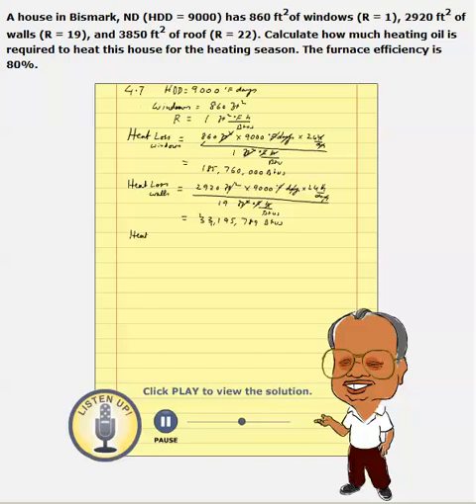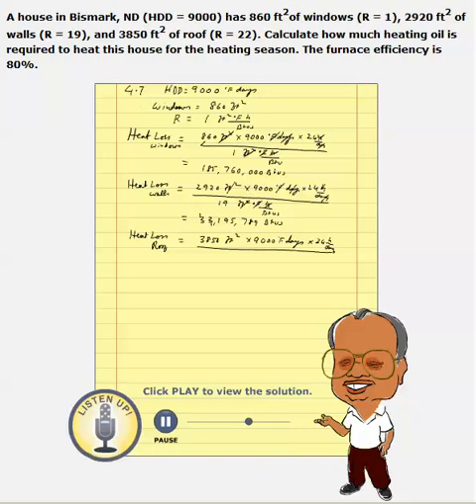Now, heat loss through the roof. The area of the roof is 3,850 square feet, times 9,000 degree days, times 24 hours per day, divided by the R-value of 22 for the roof. Canceling out the units, the heat loss through the roof is 37,800,000 BTUs.